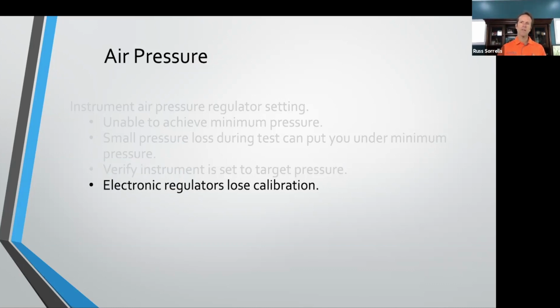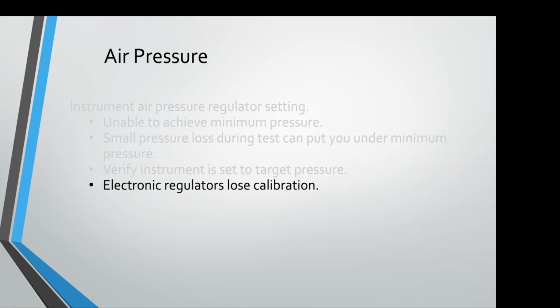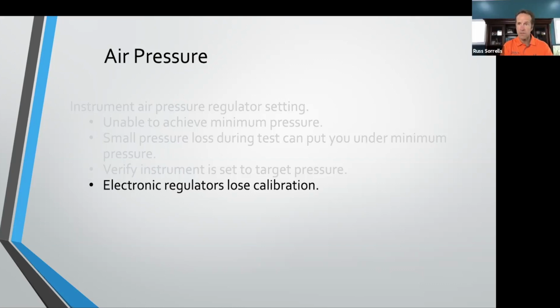Anything else with electronic regulators, Gordon, that customers should keep an eye on? Oh, the electronic regulators actually work pretty well because you do set the instrument test specific for the pressure. So it will adjust that regulator when you change test parameters. Between different test pressures, it will readjust itself so you don't have that problem. One of the things that you may need to do when you first set up an electronic regulator is actually train it, let it run through a couple tests, 5 to 10, and we have automatic set points in our instruments so that they readjust those electronic regulators to the right test pressure. Yeah, excellent. Electronic regulators are a great solution, especially when you have multiple pressure applications.